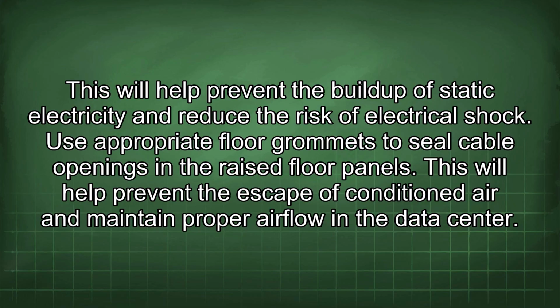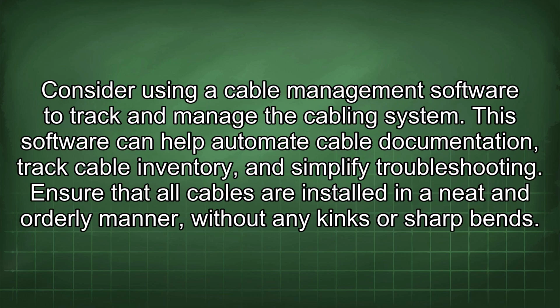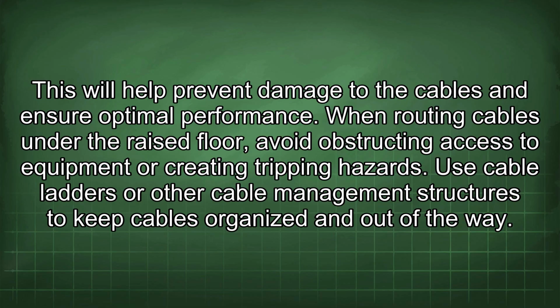This will help prevent the escape of conditioned air and maintain proper airflow in the data center. Consider using a cable management software to track and manage the cabling system. This software can help automate cable documentation, track cable inventory, and simplify troubleshooting. Ensure that all cables are installed in a neat and orderly manner, without any kinks or sharp bends. This will help prevent damage to the cables and ensure optimal performance.